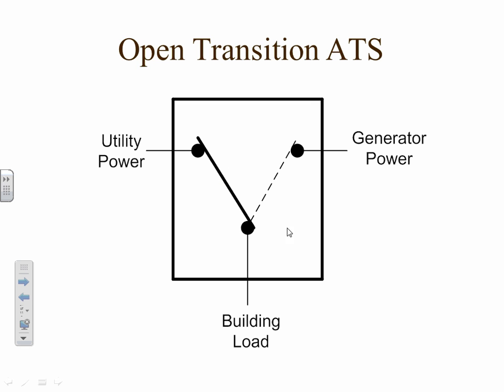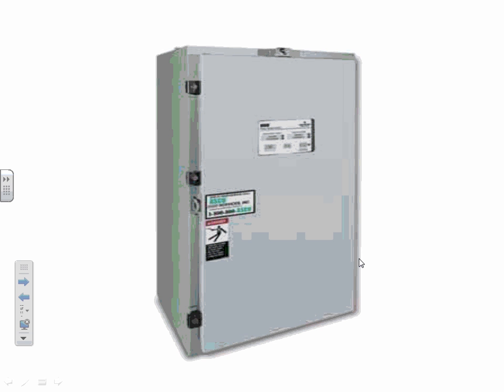But now take the instance where we're over on the generator set and the utility comes back. Okay, now we've got two live sources. So what we're going to see when we have passed our time delay on retransfer, we're going back to utility now. We flip this, but as it's transferring, it's not a lot of time. It's going to take about 100 milliseconds to get from this position over to this position. During that time, you will see a noticeable blink in the lights because you're in an open transition mode. Okay. Moving on. Here's what a picture of that switch might look like.